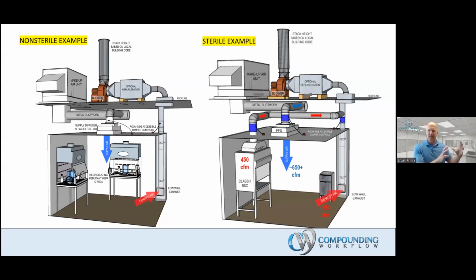Let's look at the past 5 years of business trending, and let's pull out our magic crystal ball and talk about the next 5 years of business trending. Because if right now you've got 2 powder hoods, but you're growing fast enough that in a 5-year scope you may need 2 more powder hoods and 2 more technicians, then you need to start thinking about the space and airflow requirements. That's even more true on the sterile side, because right now you've got 1 biological safety cabinet.